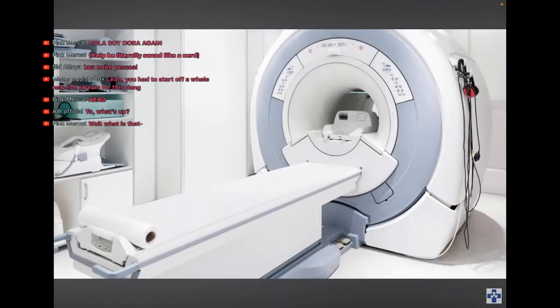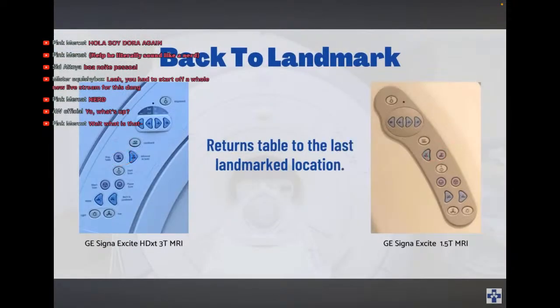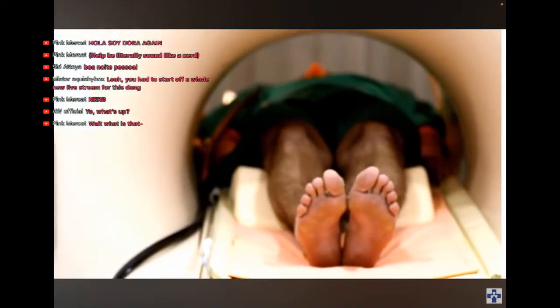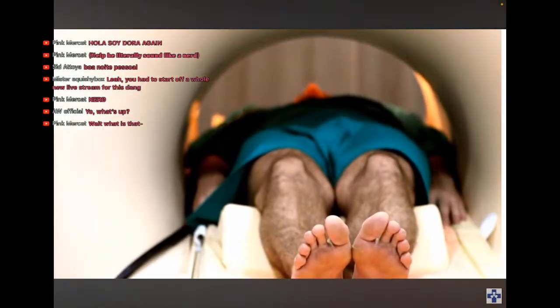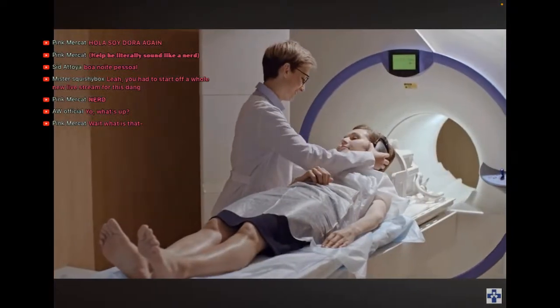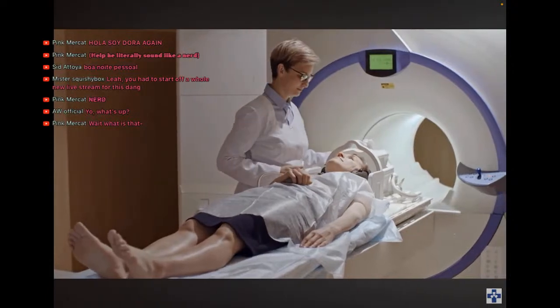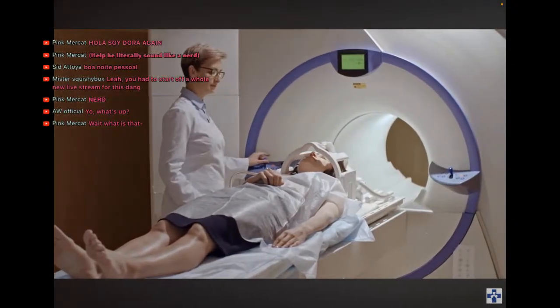This button overrides all MRI scan movement functions, including Move to Scan. The Back to Landmark button moves the patient back to the last landmark position. This button is disabled during MRI scans and emergency stop situations. The Start button restarts the scan sequence if the MRI technologist pauses the exam. The Pause Scan button temporarily stops scan functions. It is important to note that image quality may be affected if a patient's position or respiratory rates change once scan functions resume. Abort Scan stops all scan functions and ends the scan sequence.